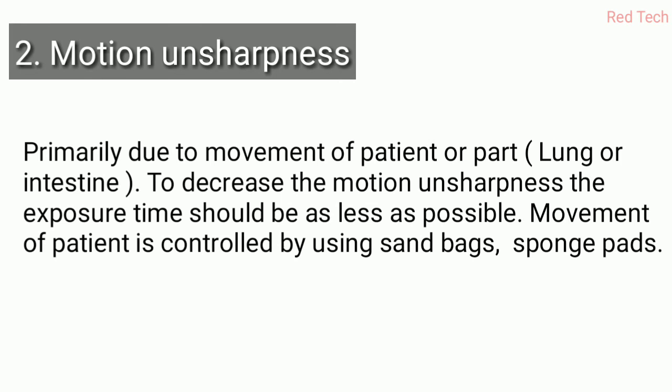Motion unsharpness is due to patient movement or movement of body parts such as the lungs or intestines. To decrease motion unsharpness, the exposure time should be kept as short as possible. Movement of the patient can also be controlled by using sandbags and sponge pads.